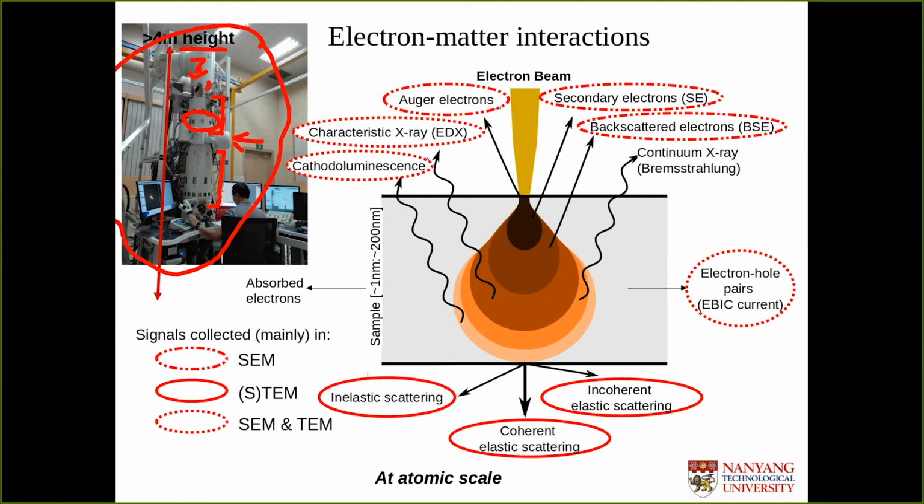When we use a TEM in STEM mode. And on the bottom part, this element is an image corrector, sorry. It corrects the aberrations when we are in TEM mode, or in plane wave illumination. Using this image corrector, we can get a resolution in the image down to around 50 picometer, and we can measure atomic displacement down to a few picometer on a good day. So this is what the TEM is.